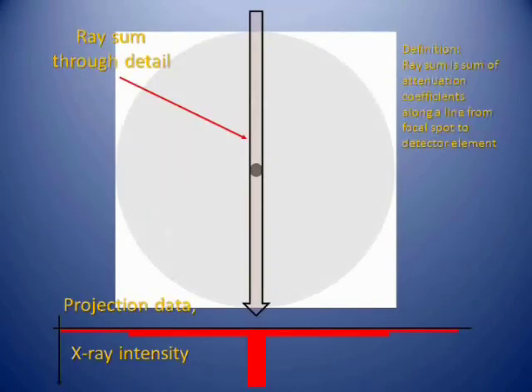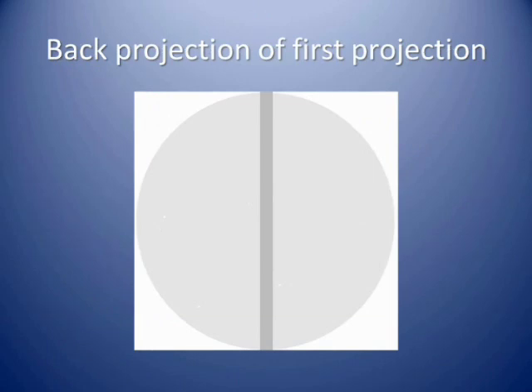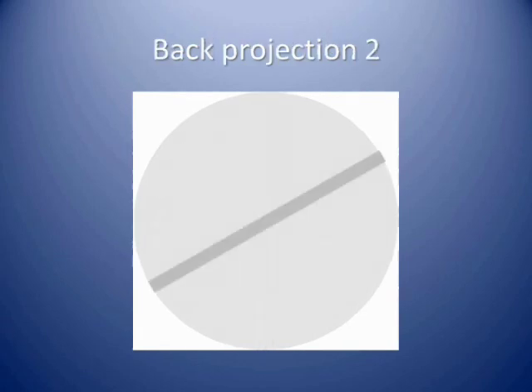If we look at the ray sum through the detail, you can see there is a considerable dip in the projection data. As a first step in reconstruction, we assume that the dip is due to a uniform material within the ray sum that has the same effect as the actual detail does, and we back project the ray sum along that direction.